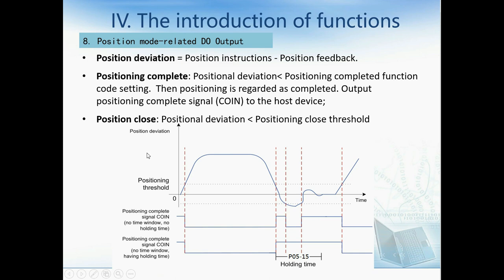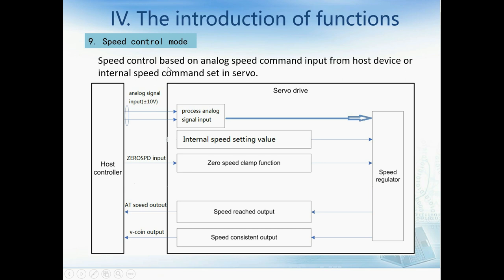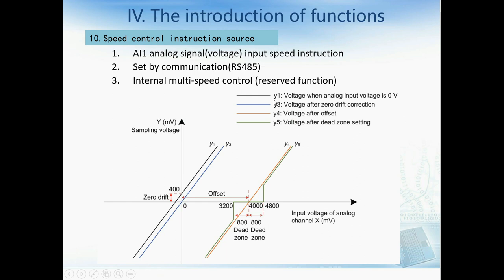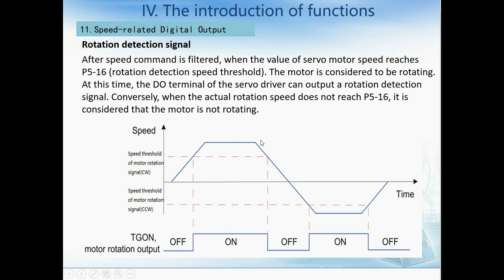Now let's talk about speed control mode. Speed control is based on the analog speed command input from the host device, or the internal speed command set in the servo. There are three sources: the first is analog input, the second is communication via RS-485, and the third is internal speed control — this function is currently reserved. Regarding speed-related digital output: after the speed command is filtered, when the servo motor speed reaches the rotation detection speed threshold, the motor is considered rotating and the servo driver outputs a rotation detection signal. Conversely, when the actual rotation speed doesn't reach the setting value, the motor is considered not rotating.